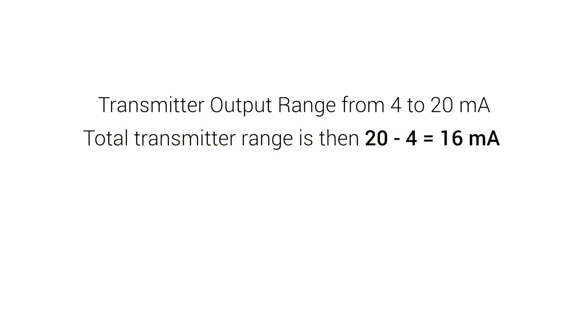The temperature transmitter has an output in the range from 4 to 20 milliamp, so the total transmitter range is 20 minus 4 equals 16 milliamp. The temperature sensor has a temperature range from 0 to 100 degrees Celsius, so the total temperature range is 100 minus 0 equals 100.